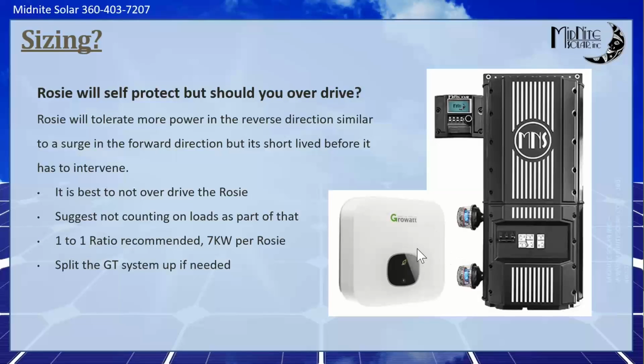So we suggest one-to-one ratio. Make sure the grid tie inverter is no more than 7 kilowatts per Rosie, and or split up the grid tie system if it's made of inverters that allow you to do that, like microinverters or multiple string inverters. Just for optimal system performance and lack of callbacks, that's going to give you that bulletproof system.